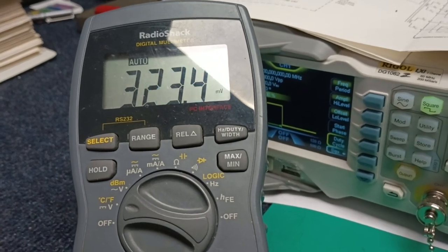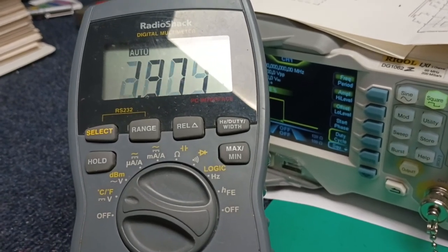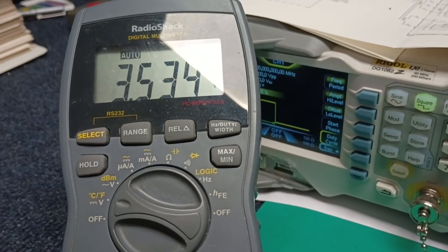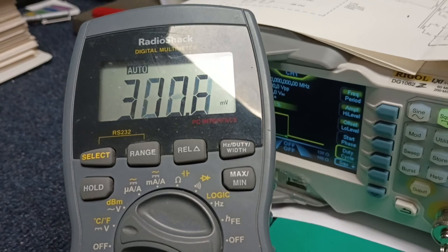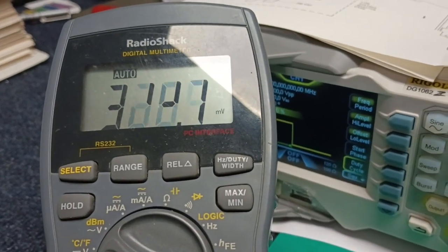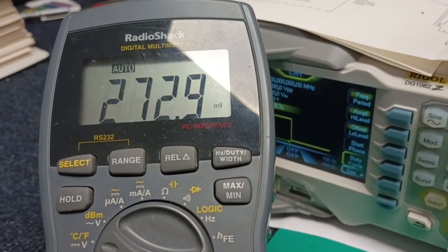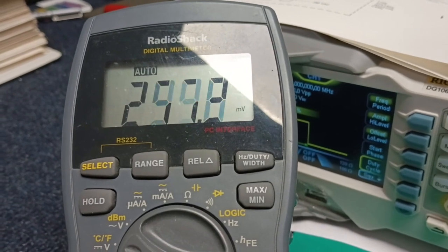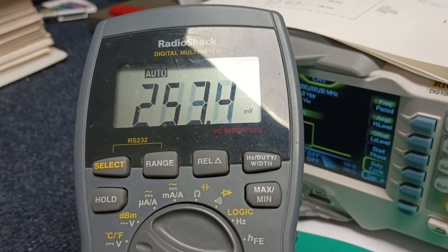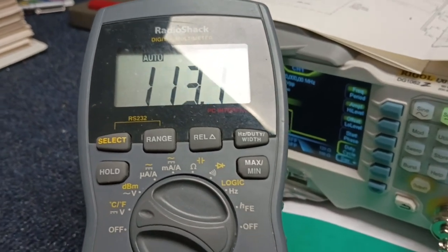.300 some millivolts. A couple of volts with a really unstable reading. The so-called earth terminal, same. The so-called earth terminal, about the same reading and same kind of reading as touching L1. And this immediately tells us that there's AC floating around here.